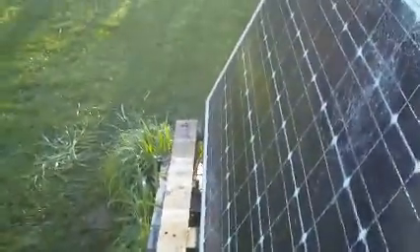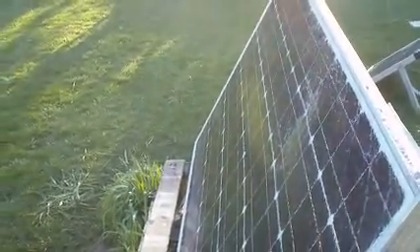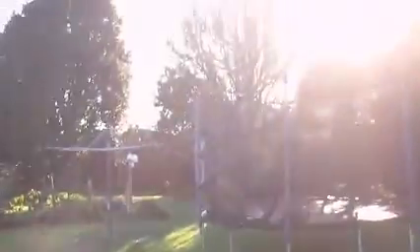Before we put it back up, we'll give it a ground test. I'm measuring the short circuit current. The sun is over this way, but as you can see the panel is pretty much pointing in the opposite direction of the sun, so we're not going to get much current. But the main point is that the current is fairly uniform across all the sections - each string.